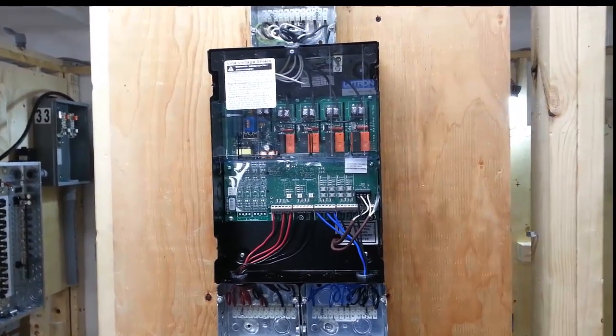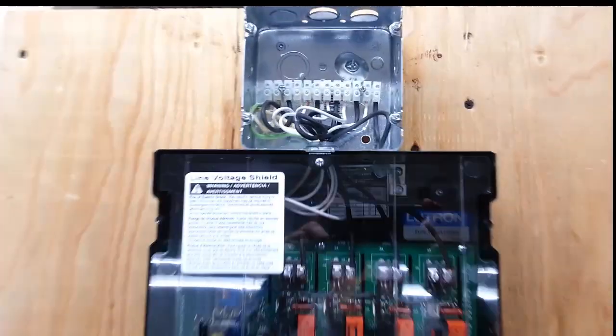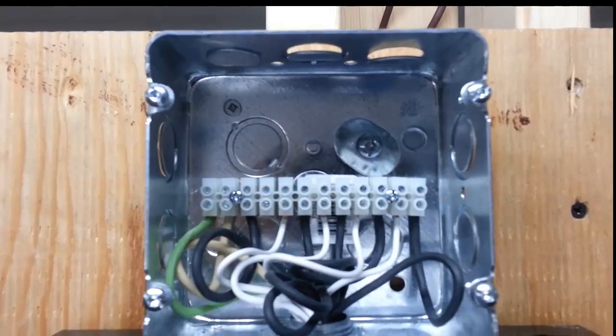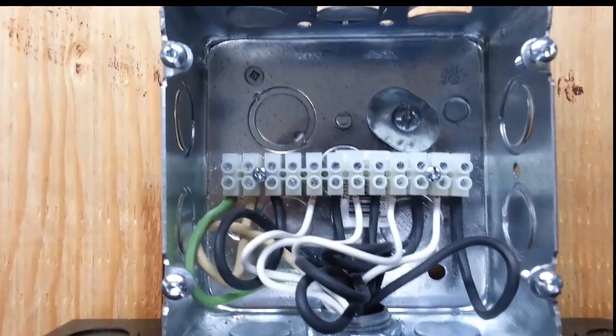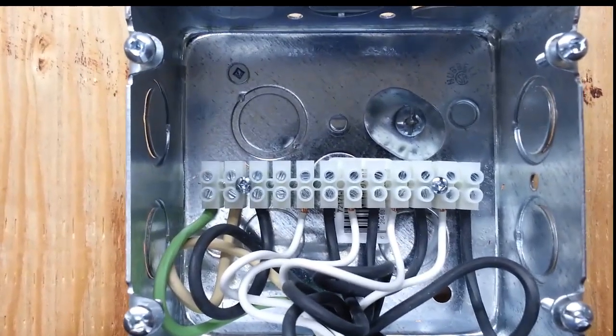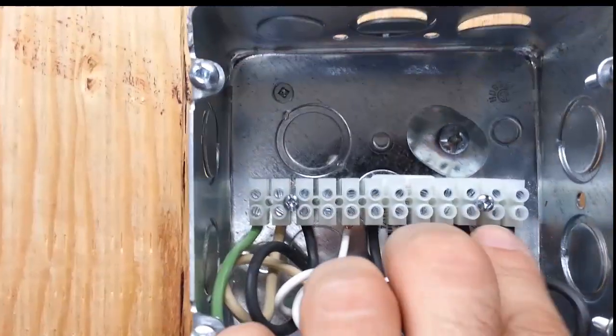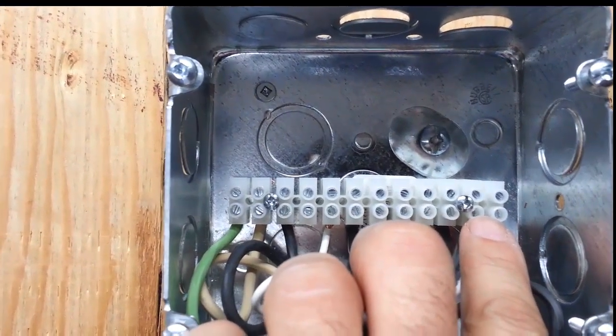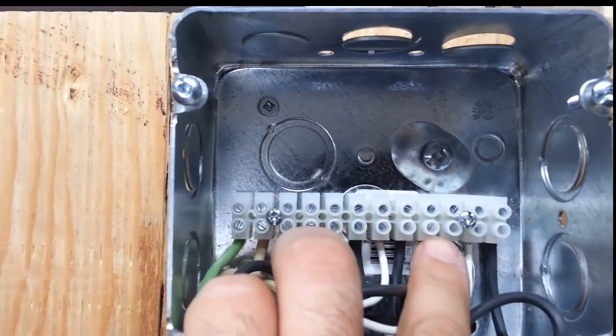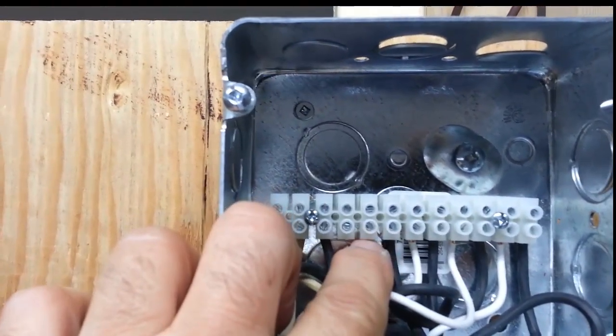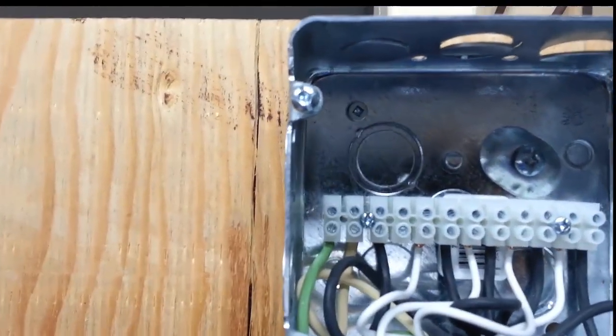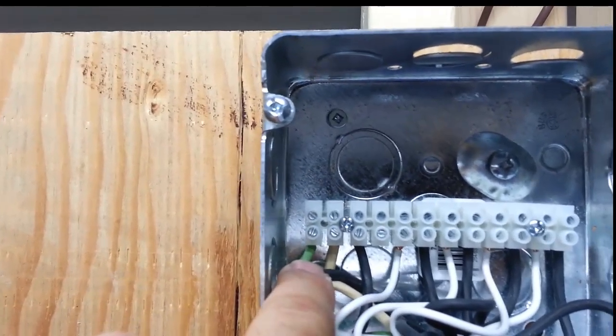The actual 120 volt connections will happen in this box up here. You see it has black and white wires. So you have your neutral and your hot. And you have basically four lines or four loads that this unit can handle. So there's one load here. Another load here on the black and white. Third load on the other black and white. And the fourth load on the other black and white. The black and white on the far left is the actual feed that goes into the panel that feeds the unit.